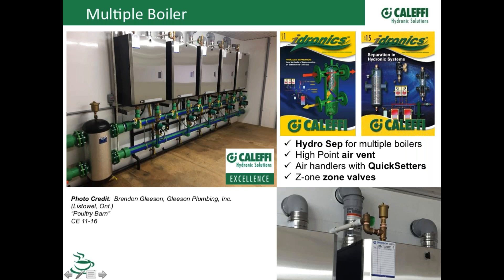By using Aquatherm piping, our larger hydro separators come in a flange version. All he had to do was get a companion flange and go right to that fusion weld pipe — a really quick and clean connection. I've also seen isolation valves, like a butterfly or wafer valve, put in here so you could isolate and add into the system someday. He's got isolation at the boiler, and I've seen it where they isolate all four separators too. A really nice piping job.